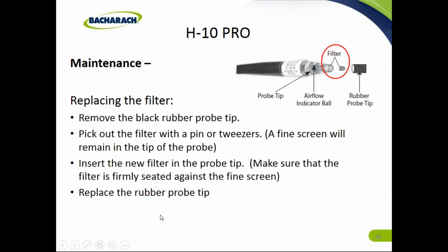How do you replace it? Remove the black tip of the probe. Pick out the filter with a pin or tweezers. There will be a fine screen that stays in there. Insert a new filter in the probe tip and make sure it rests against that fine screen. Put the rubber tip back.